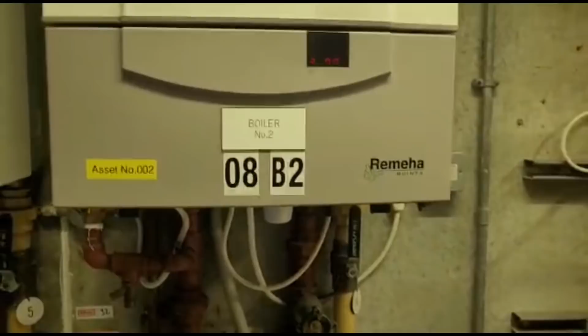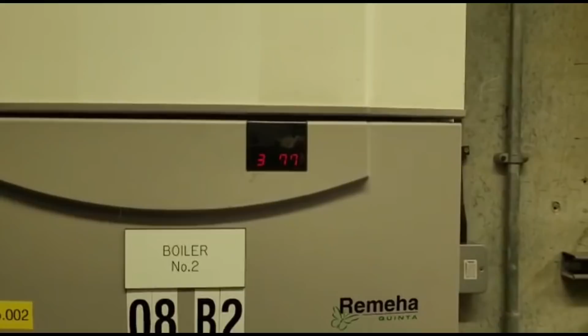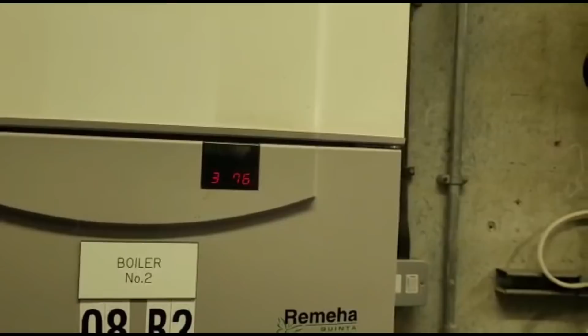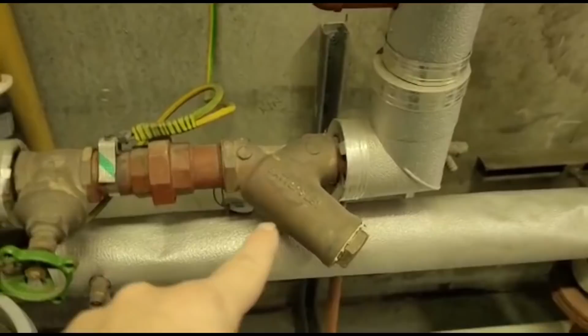Right, so first job before we change these pumps is to get this system water a little bit cooler, one, so it doesn't crack a heat exchanger, because heat exchangers in these will just start kettling. And also to get the water a little bit cooler, because there's quite a bit of pipework. Even though you've got a non-return valve here and your gate valve there, you've still got a fair leg of water.